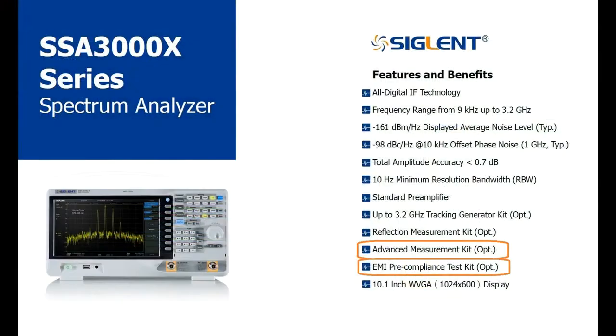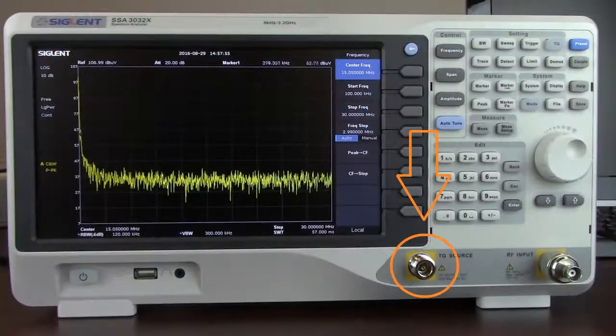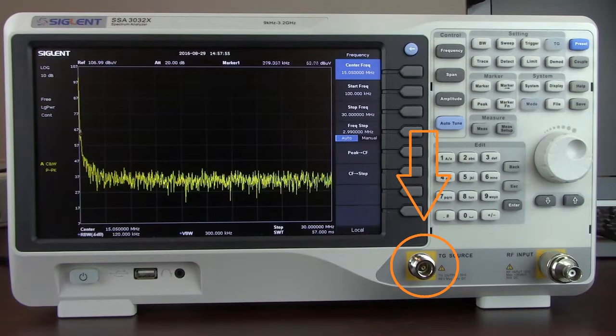The final option I'd like to cover today is the tracking generator. A tracking generator is a swept RF source that follows the analyzer frequency steps. It's typically used to test filters, amplifiers, and cables. The tracking generator hardware from Siglent is included with all versions of the SSA 3000X family.